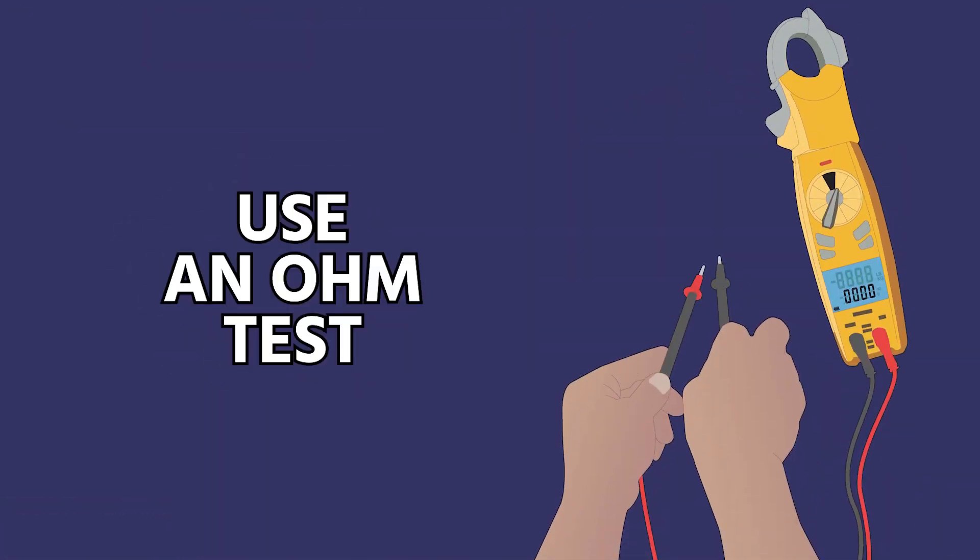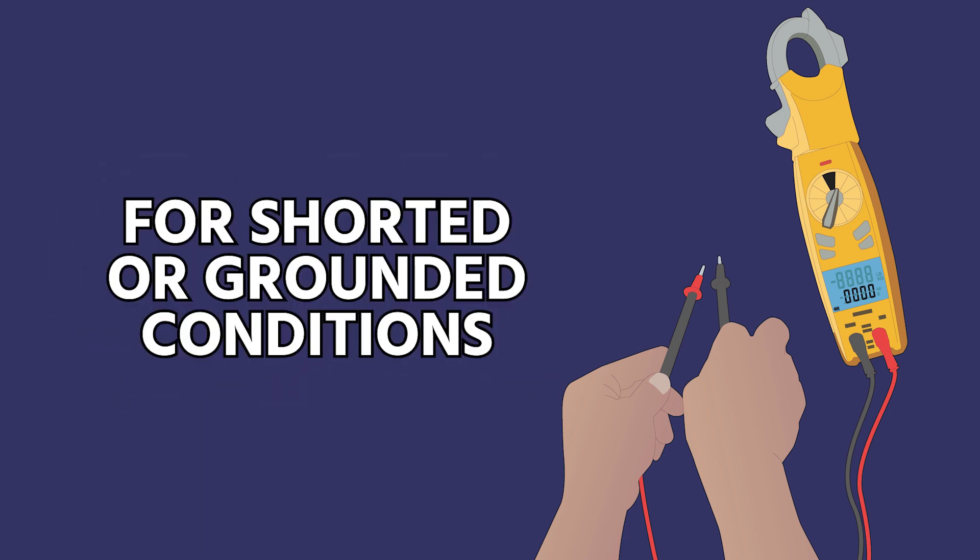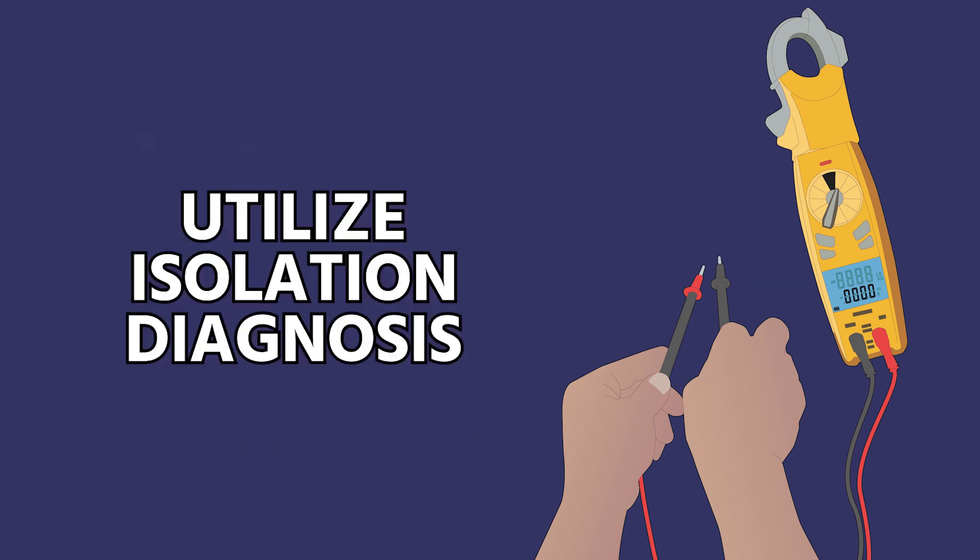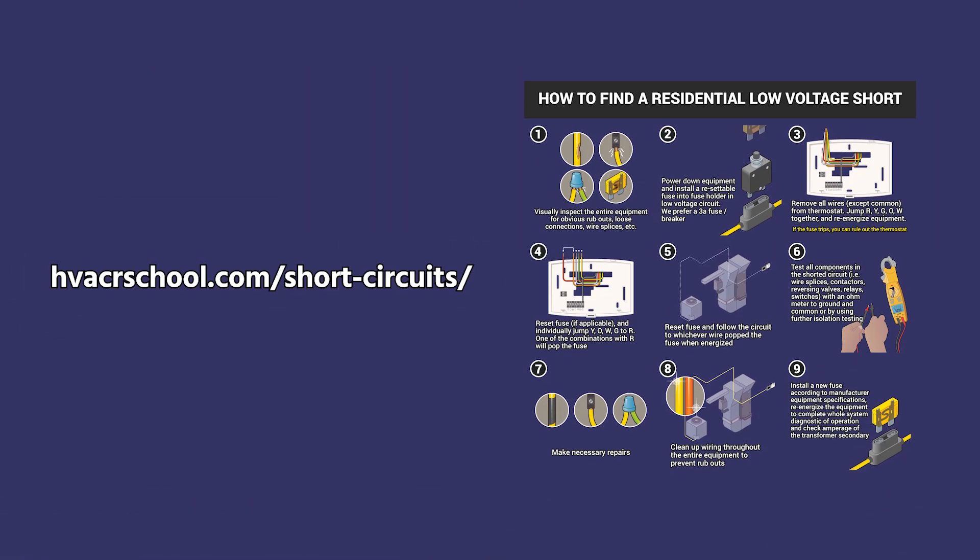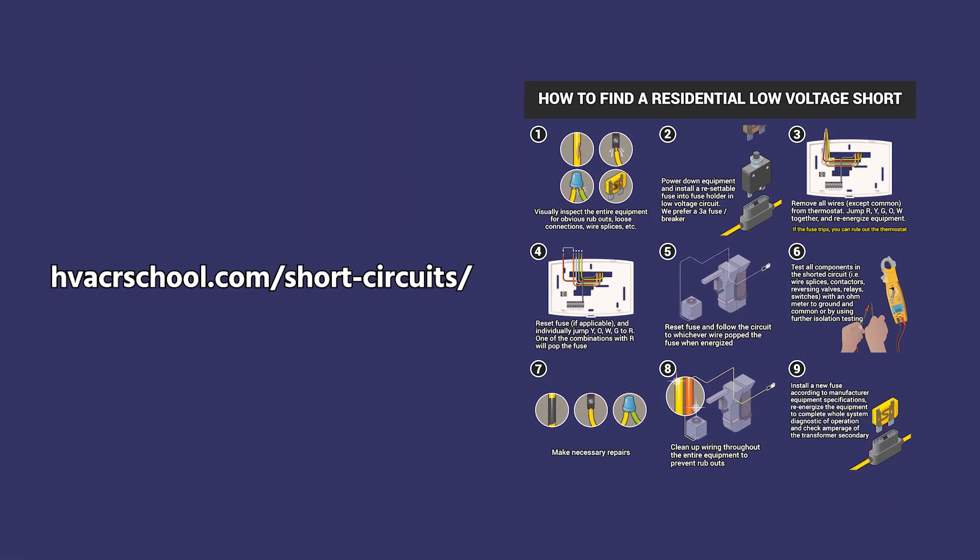But you want to follow best practices as far as use an ohm test, check all of your loads, check your circuits for shorted or grounded conditions, and also utilize isolation diagnosis. We've done another video on isolation diagnosis of low voltage circuits and we have a nine panel process for that on the HVAC School app for finding low voltage shorts.